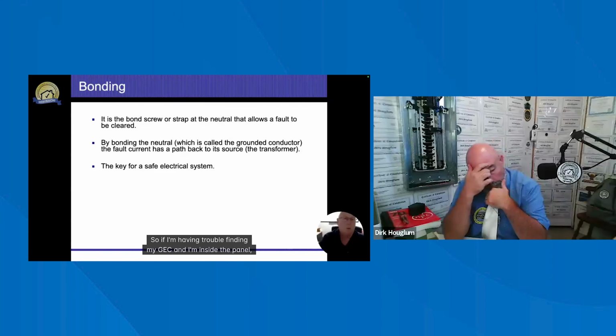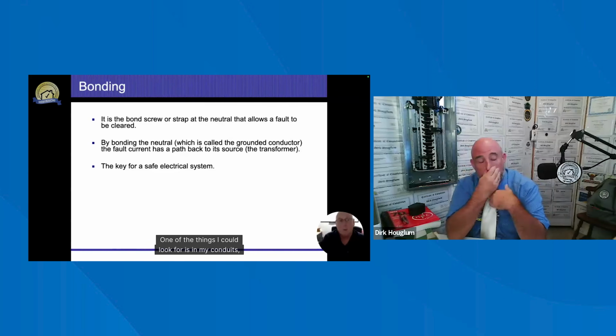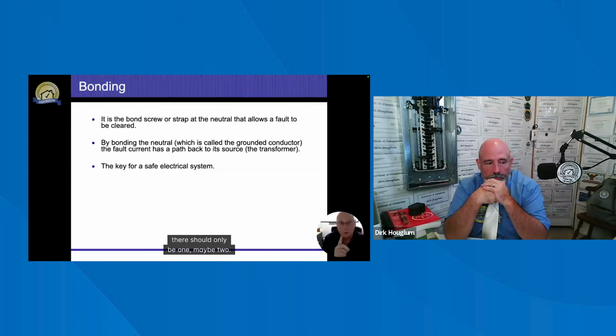So if I'm having trouble finding my GEC and I'm inside the panel, one of the things I could look for is in my conduits, there should only be one, maybe 2. You know, if they go one to the water pipes and one to a ground rod outside, I might have 2 of them. But they should be one wire inside that conduit all by itself. All right. If any other wires do share and go in there, that's going to end up being a problem. Nothing else goes in that GEC by itself.